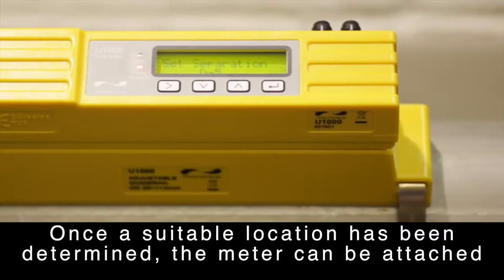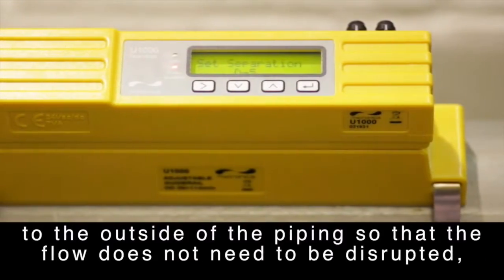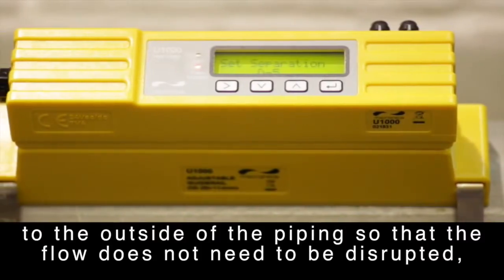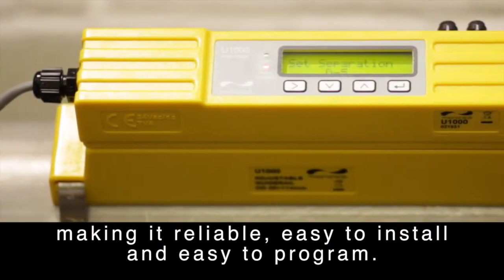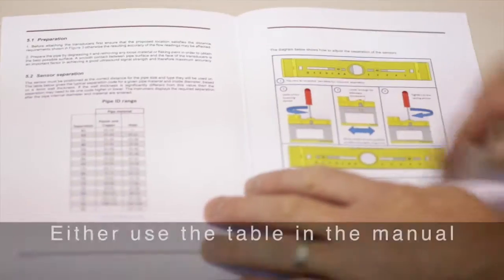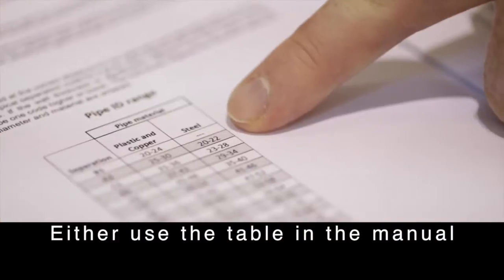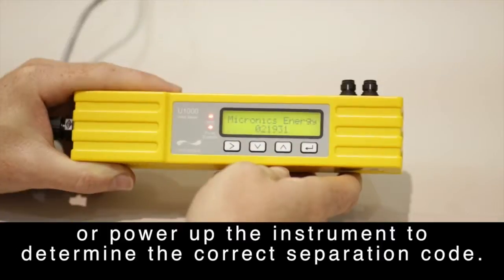Once a suitable location has been determined, the meter can be attached to the outside of the piping, so that the flow does not need to be disrupted, making it reliable, easy to install and easy to program. Either use the table in the manual or power up the instrument to determine the correct separation code.